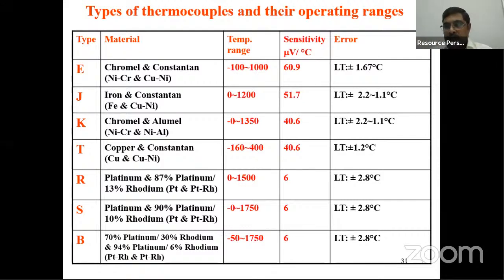Whenever there is a wet environment, or if you are going to measure the temperature in a water medium or where liquid is present, please don't use a J-type thermocouple. In the presence of water or moisture, a J-type thermocouple will generate additional galvanic EMF, which will lead to error. And again, a K-type thermocouple is not advisable where the environment has high vibration and noise. So that cannot be used.